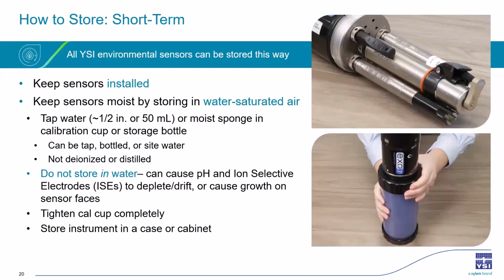So we're going to get into how to store for short term. First, I do want to note that all YSI environmental sensors can be stored this way, and these pointers are genuinely going to be true for other brands as well. All you're going to want to do is store the sensor in a moist air environment, otherwise known as water saturated air. And to do this, you're just going to put a small amount of tap water or a damp sponge in a calibration or storage cup, and then just tighten the cup onto the sensors.